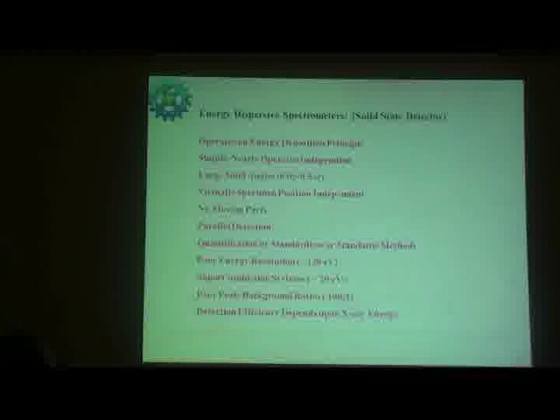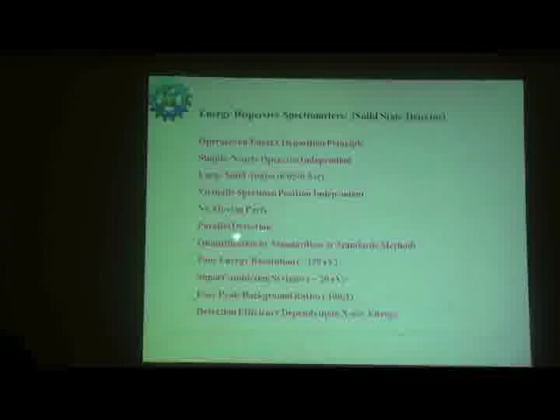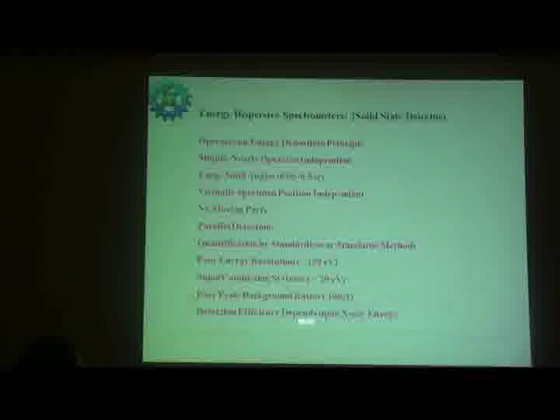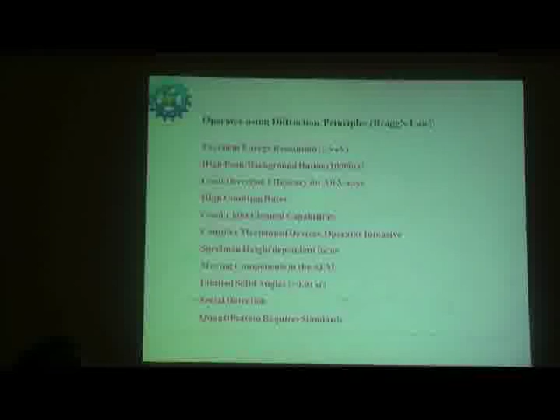So basically it operates on the energy dispersive principle. You have large solid angles. This is specimen position independent; you don't have to change the position. No moving parts. Parallel detection, quantification by standardless and standard methods. Here the energy resolution is something like 130 electron volts, and with a superconducting system you can go to better resolution. The peak to background ratio is something like 100:1.